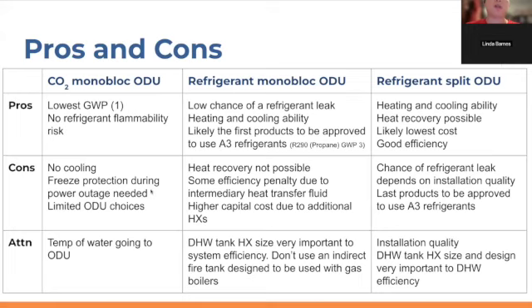And so the desire for a CO2 system is not to multi-pass, meaning circulate the working fluid multiple times, and therefore end up with warm inlet water coming back into that outdoor unit. It really kills the efficiency of the CO2 refrigerant cycle if you get warm water. Typically, warm meaning anything above 80 Fahrenheit incoming fluid would be really bad for a CO2 monoblock system. So therefore, they typically do straight water. But one of the downsides of straight water is, well, it freezes, and if you happen to have below freezing weather conditions and a power outage, that can be really bad and could damage your CO2 monoblock outdoor unit.